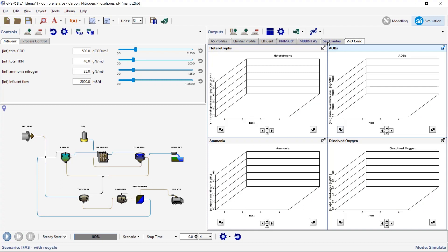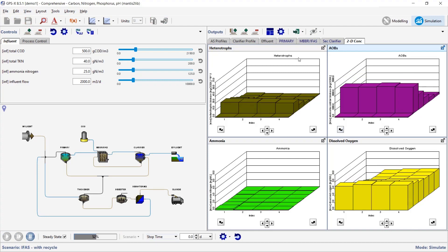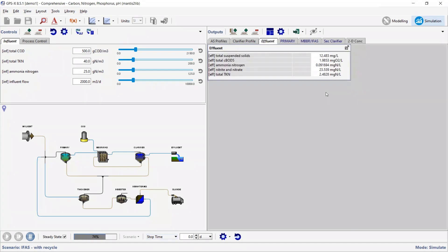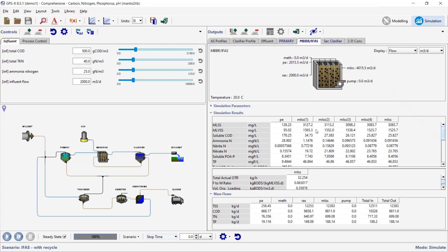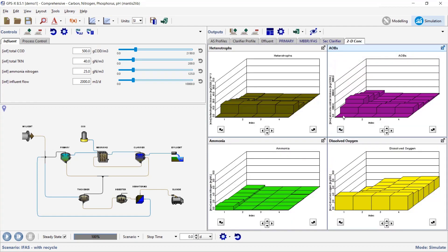That was for MBBR. Now I've made a scenario with IFAS — basically I just turned on the recycle and I'll run it again. With the RAS recycle at 1Q and everything else the same, we're now containing a lot more solids — it was around 8 before, now it's 12. That's because we now actually have a mixed liquor of about 3000 along with all our biofilm biomass. We can see there's less of a gradient for heterotrophs now.